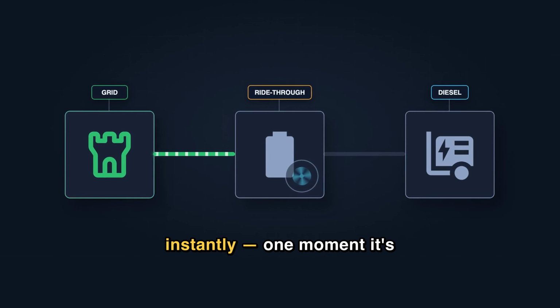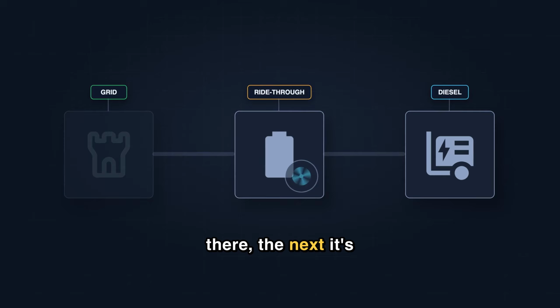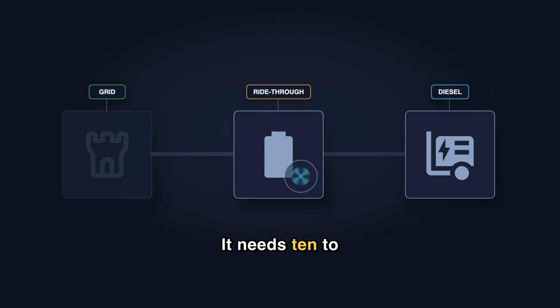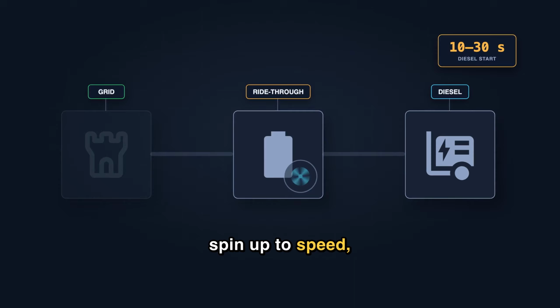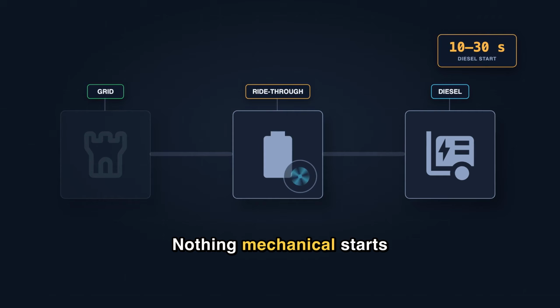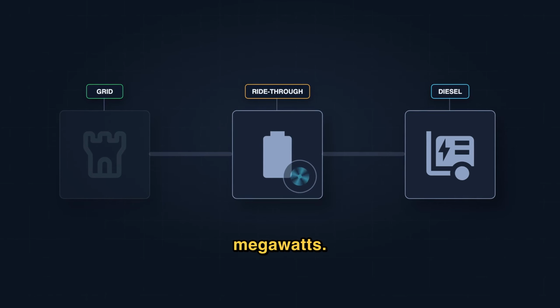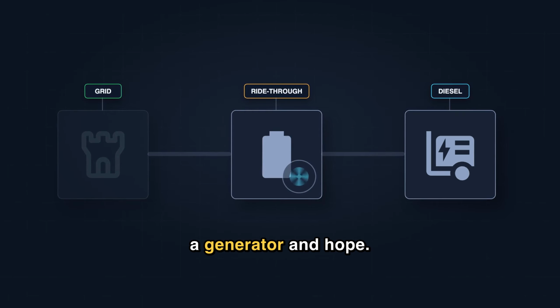Utility power fails instantly. One moment it's there, the next it's gone. But a diesel generator is a cold engine. It needs 10 to 30 seconds to crank, spin up to speed, and take the full load. Nothing mechanical starts that fast, carrying megawatts. Think about it. You can't just wire the servers straight to a generator and hope.